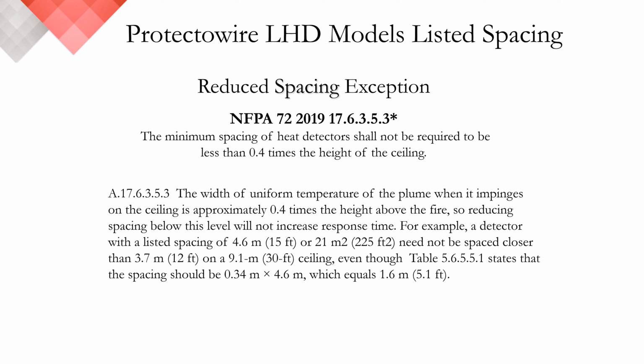In NFPA 72, Annex A provides explanatory material to help provide some understanding to these guidelines. Annex A, Section 17.6.3.5.3, provides the following. The width of the uniform temperature of the plume when it impinges on the ceiling is approximately 0.4 times the height above the fire. So reducing spacing below this level will not increase response time.